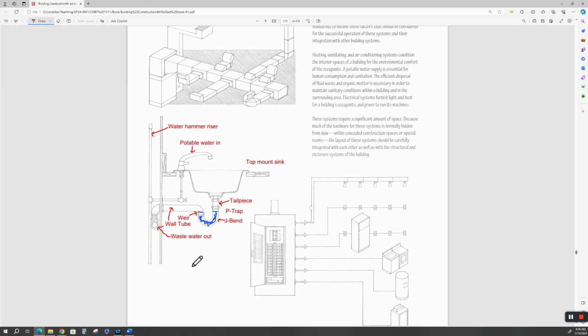So if you're in a building at the Cypress Center, classroom CY129, there's a storage room right behind the concrete masonry unit wall, and in that storage room is a floor drain. About once a year, depending on the relative humidity and how hot it is and how much air is being sucked as makeup air out of that storage room, the P-trap will evaporate, the floor drain, and you'll start getting sewer gases into the classroom.